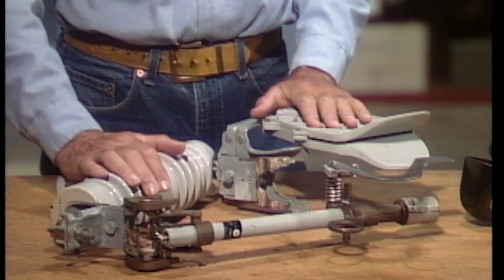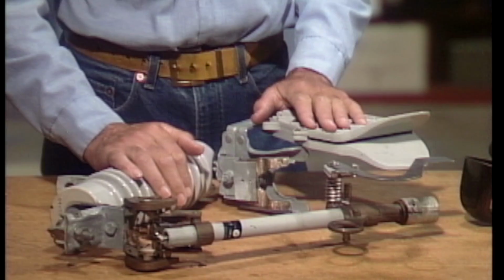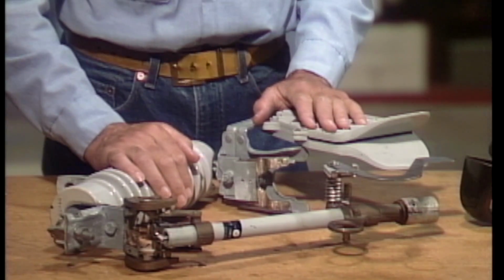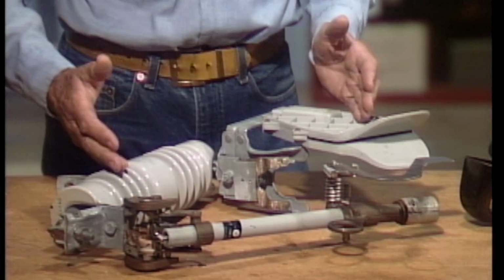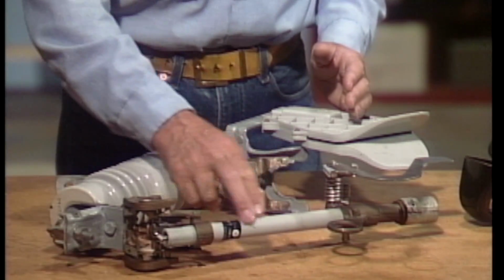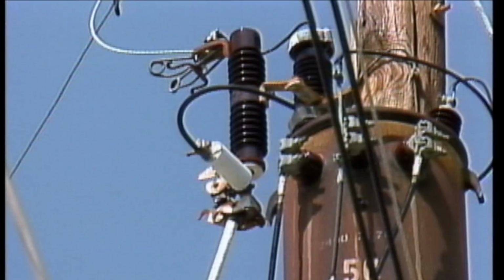There are several different types of fused cutouts, including open cutouts and enclosed or box-type cutouts. Now, this is a typical open cutout. An open cutout is one in which the entire cutout assembly is exposed. In this cutout, the fuse link is inside the fuse barrel. Some open cutouts have attachment points to enable an independent load break device to be used to open the cutout. The load break device provides a way to safely open the cutout under load.